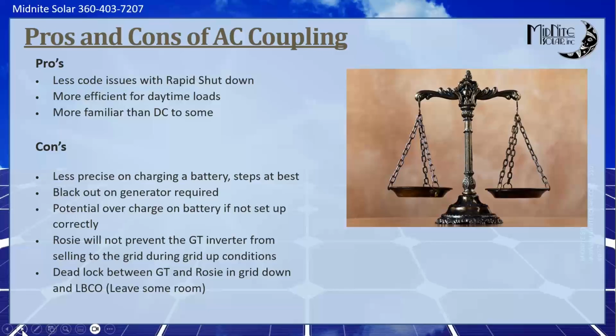Another one is the potential overcharge of your battery if it's not set up properly. And this we'll talk about a little bit in the test of the system, the functional test. But this is one of the big ones that we see, where the installer will put it together and not actually enable the AC coupling or the frequency shift, or not put the blackout relay in. And then the battery-based inverter has no control. So it cannot control the charging when it's running in reverse like it can when it's in forward. It has to use that power.